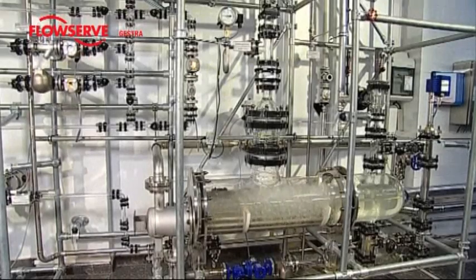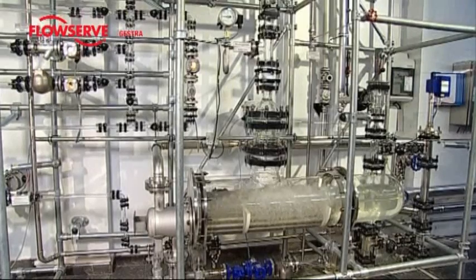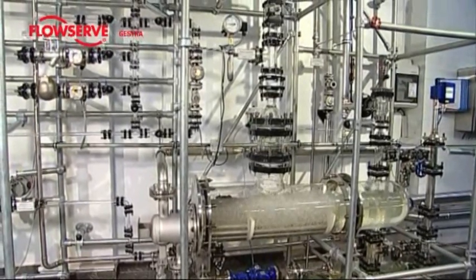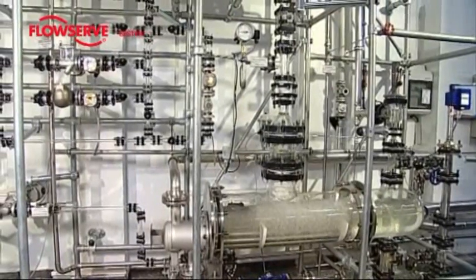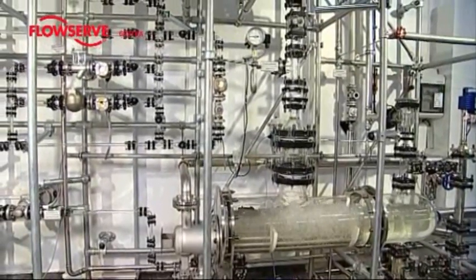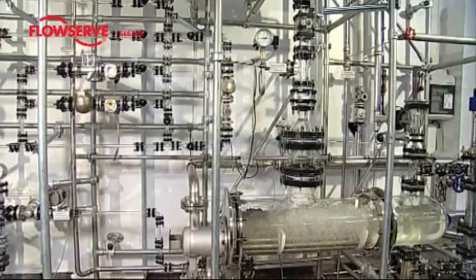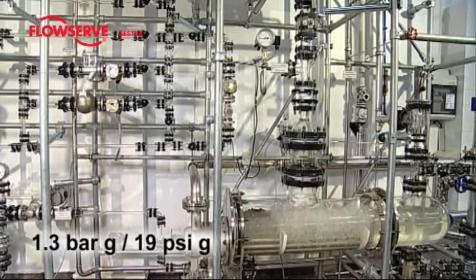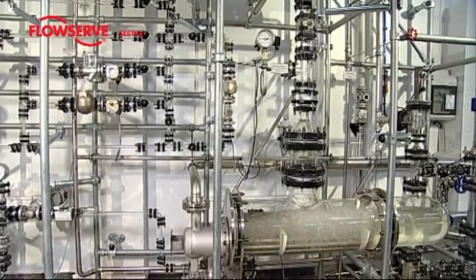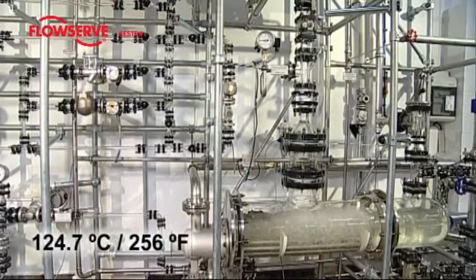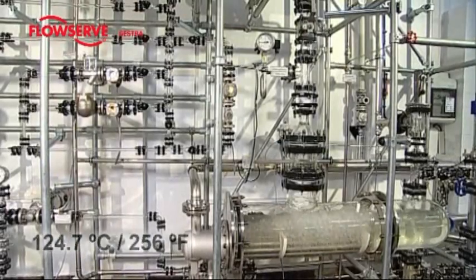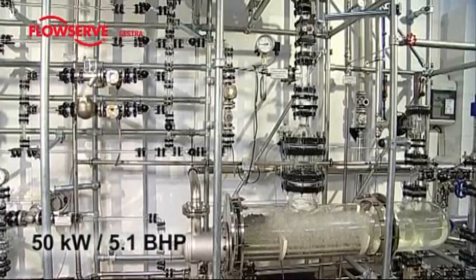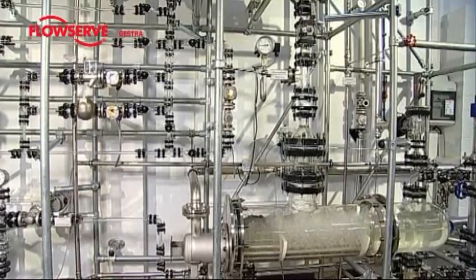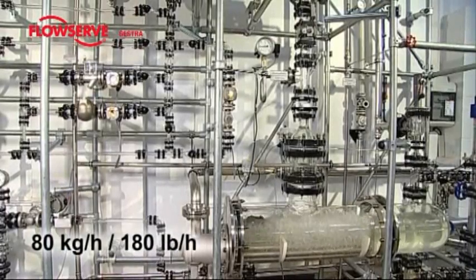This video looks at condensate discharge using various kinds of steam traps, as demonstrated in the glass steam system of Gestra AG, Bremen. The steam system consists of a secondary steam generator with a service pressure of 1.3 bar G, corresponding to a saturation temperature of 124.7 degrees centigrade. The capacity of the steam boiler is 50 kilowatts, which yields a steam flow rate of 80 kilograms per hour.